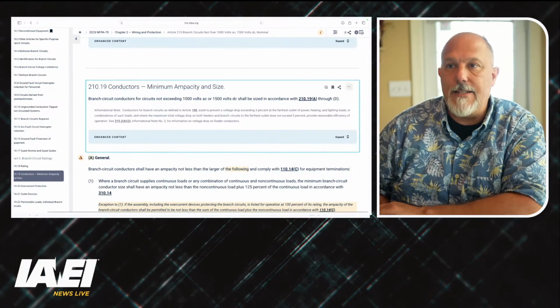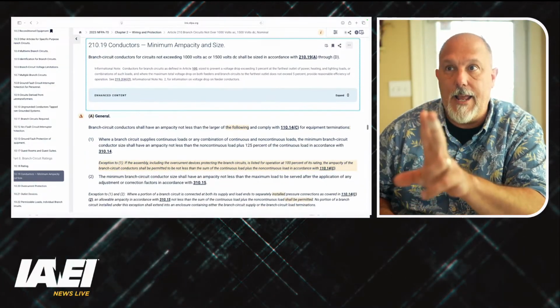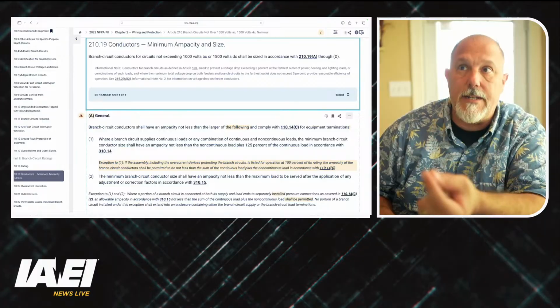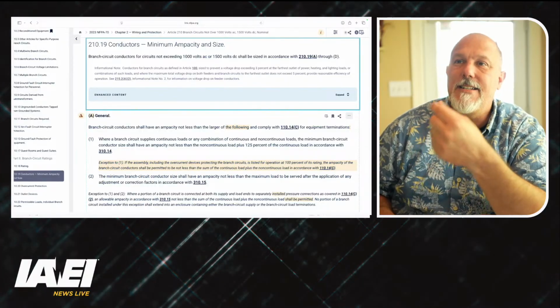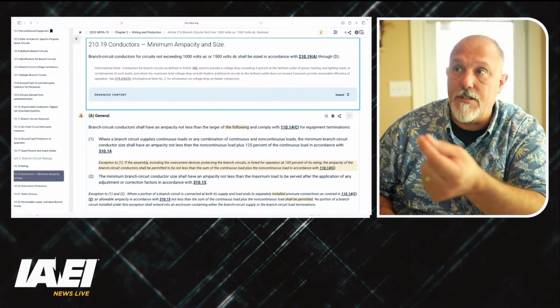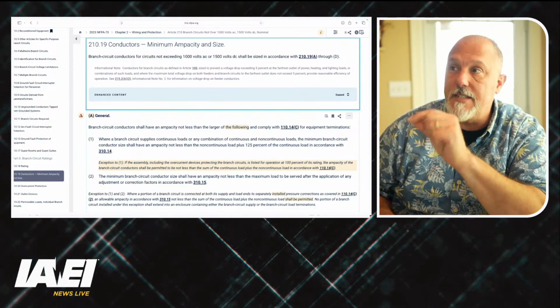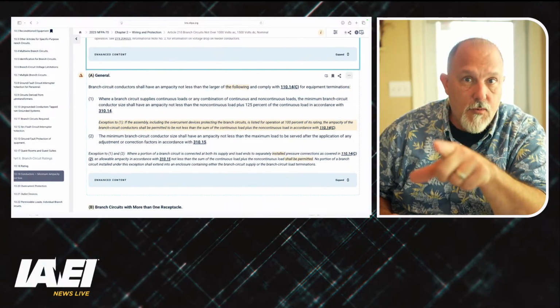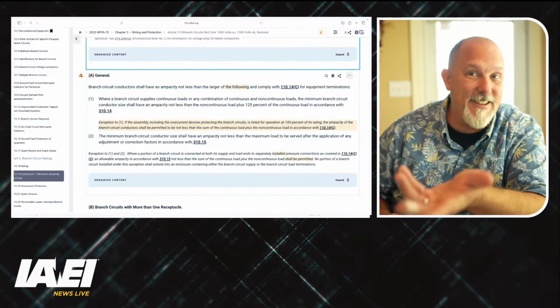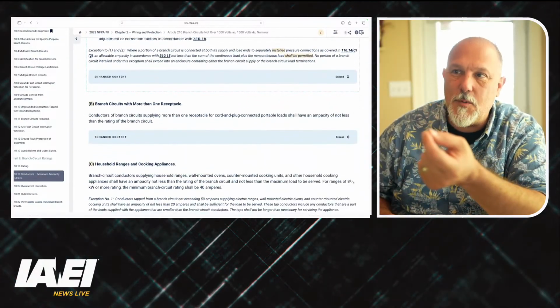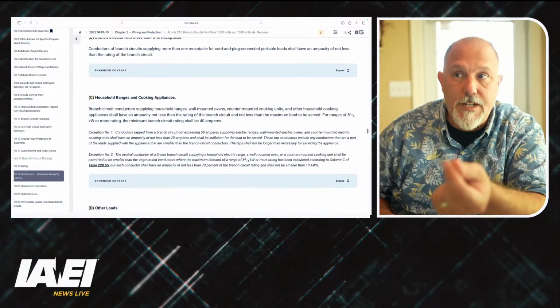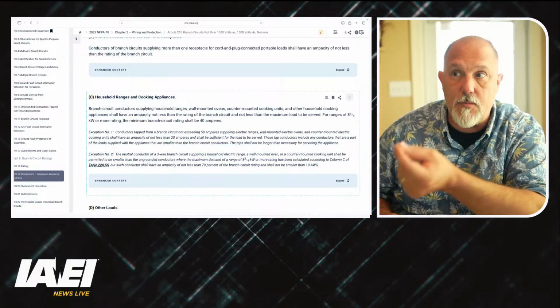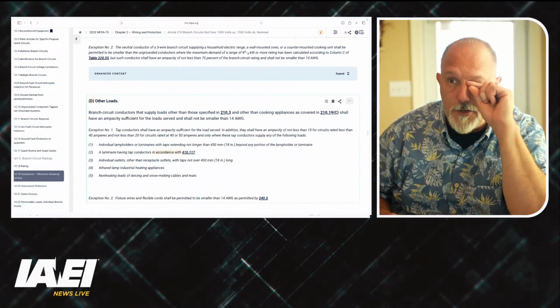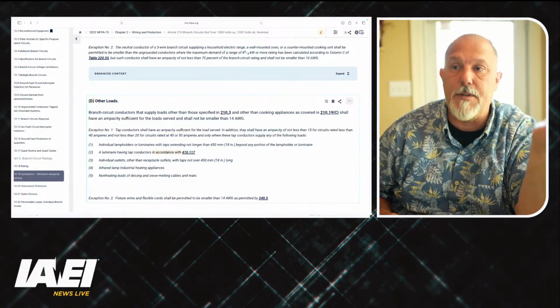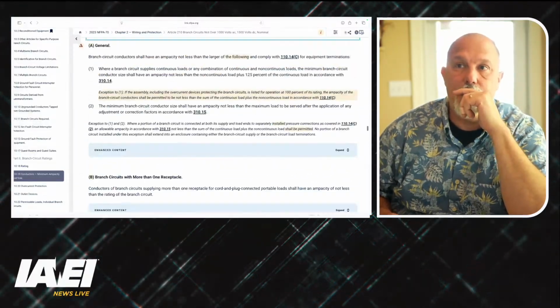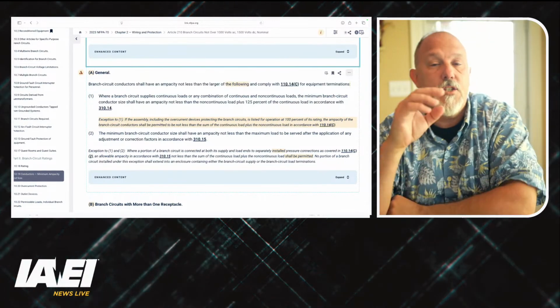So 210.19 tells us we have two calculations in A. 210.19, I have a hard time with 19, tells us branch circuit conductors for circuits not exceeding 1,000 volts AC, 1,500 volts DC shall be sized in accordance with A through D. A is your general requirement. That's where everybody goes in general, right? Because that's why they call it general. And then you have branch circuits with more than one receptacle in B, household ranges and cooking appliances in C. There's special requirements there. And then they have other loads like your individual lampholders, luminaires with tapped conductors, individual outlets. And that's D. We're going to focus on A. So A, okay.